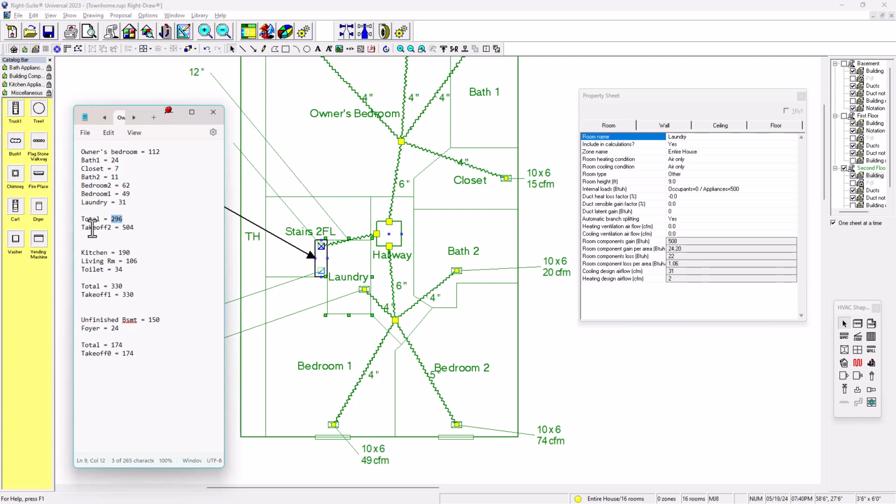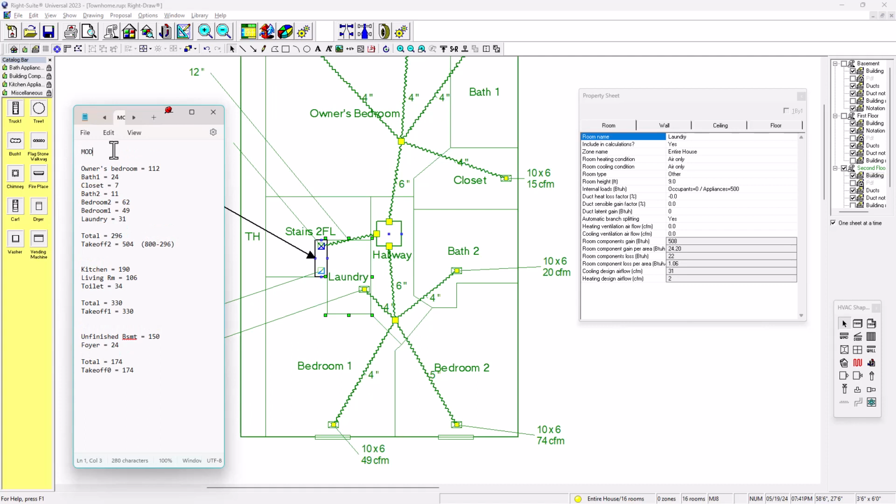Okay, so what I do in here, for this takeoff 2 means second floor, is going to be 504, I'm sorry. What is 504? 504 is 800 minus what we already have taken to supply all this second level, right? Which is minus 296. See, 800 CFM minus 296. The remaining is 504, okay? And then keep in mind, what is the mode? Mode is cooling, okay? The mode is cooling because it's not simultaneous.